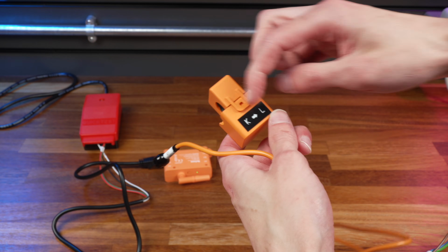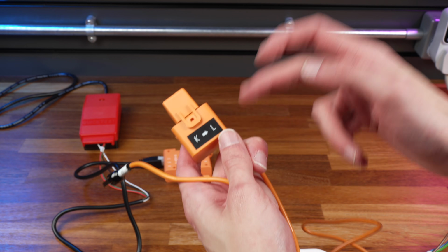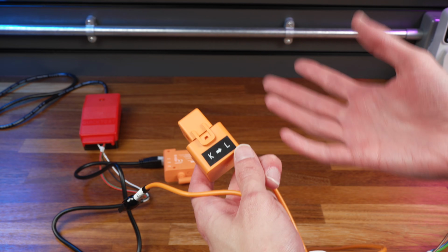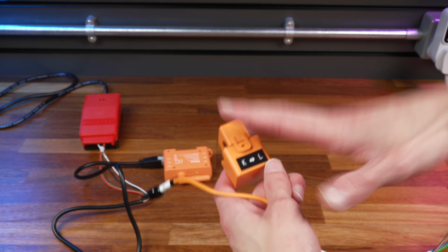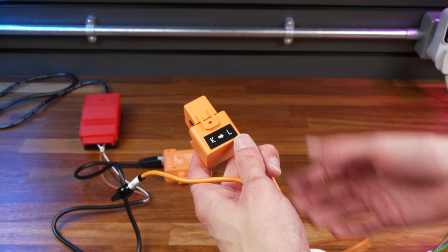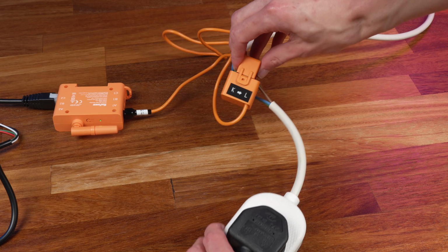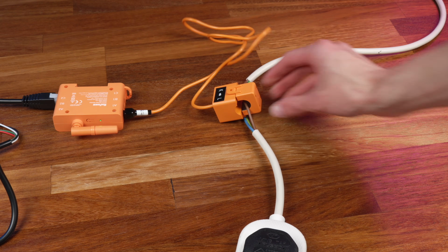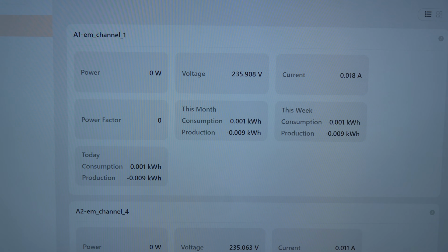So there we go, I've now relabeled all my CTs, so I'll be using them this way around for the remainder of the video. Of course, this may be different to yours; your CTs might be labelled correctly from the factory. I would just recommend testing them before you go and install them into a live environment. And there we go, so that's the CT now installed the correct way around on the cable. If we turn on the load, wait for a second for it to refresh, we can see we're now getting a positive value for power and a positive power factor.